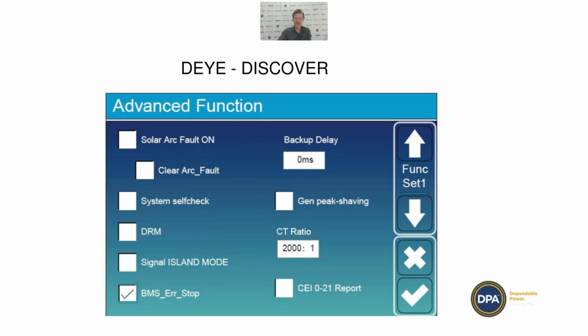Otherwise, you switch that off, the inverter won't work if you don't have it switched off. And then BMS error stop - if you're doing closed loop communications, you need to have that on. What that means is that when it loses communications, it will stop instead of just continuing with whatever the previous command was.